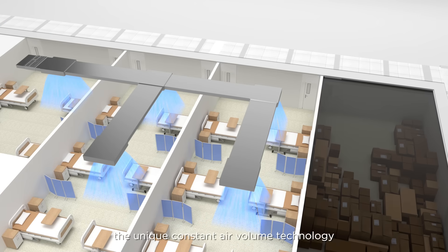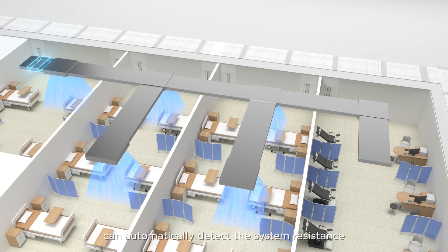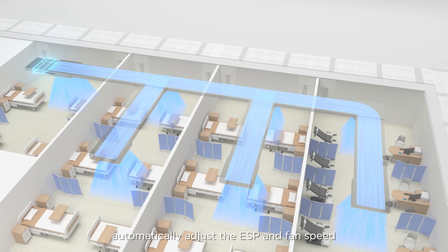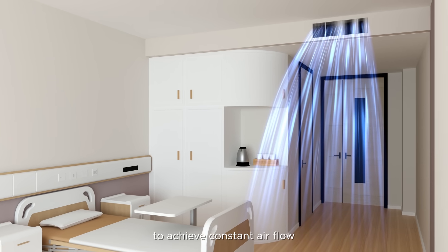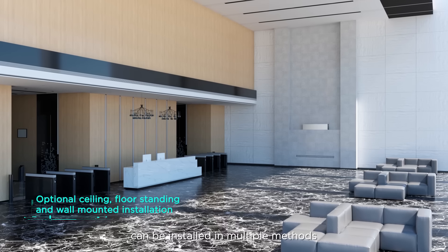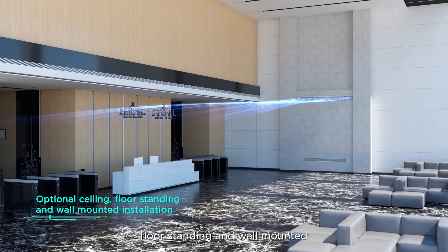The unique constant air volume technology can automatically detect system resistance, automatically adjust the ESP and fan speed, and correct design and installation errors to achieve constant airflow. The new flexible ESP ducted unit can be installed in multiple methods, including ceiling, floor standing, and wall mounted configurations.